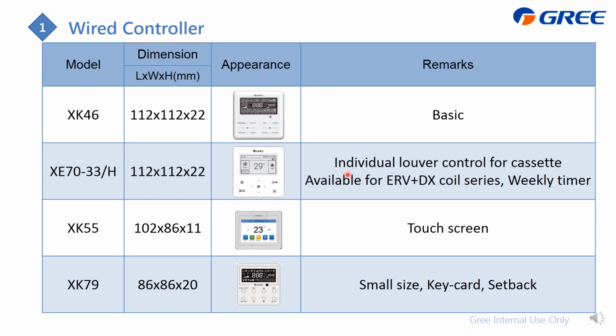It can individually control the cassette type louver, and it is also special for the ERV plus coil. Besides, it has the weekly timer, which is convenient for the customer to control. We also put all the commands, functions and parameters directly on the screen, so on site you don't need to memorize the codes for different functions or parameters. You can just change the displayed value on the screen directly.